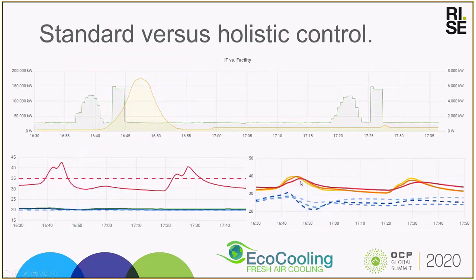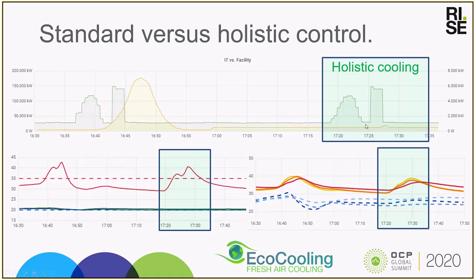We turned the coolers into holistic cooling mode, and what you can see here is that we didn't really need to do this big jump here. By a little bit of clever process control, we only needed to ramp up the fans just slightly at the point when the maximum load was running for just over a minute. So you can see here the contrast in the two, that the fan energy saved is substantial. In terms of the temperature seen by the IT, pretty much the same. In terms of the set points, the supply and return temperature within the hot and cold aisle, that's the same as well.